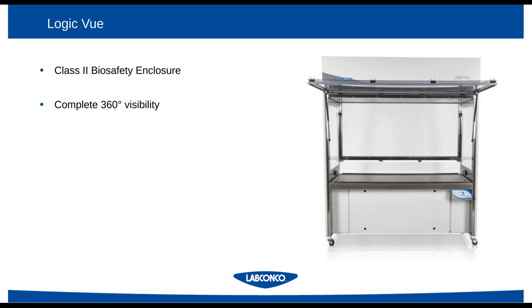Certainly as automation systems run without user input or interaction, it's important to quickly glance and see that the system is running safely. Also, just on the note of accessibility, many times automated liquid handlers can be several hundred pounds, and to be able to support access without completely dismantling the system for service, this unit is provided with both a front and a rear fully loading sash.